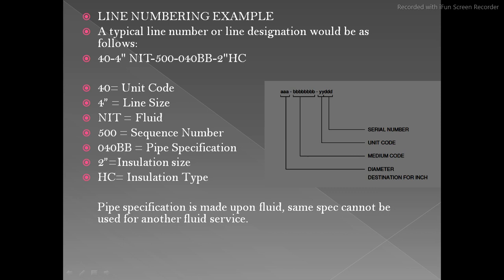Here is an example of a line number: 40-4-inch NIT-500-040BB-2-inch-HC. The '40' stands as a unit code, '4 inch' is the line size, 'NIT' is the fluid service, '500' is the sequence number, '040BB' is the pipe specification, '2 inch' is the insulation size, and 'HC' stands for insulation type.